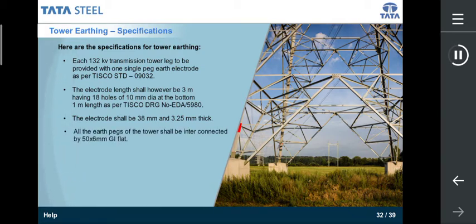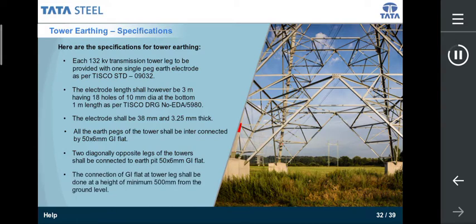All the earth pegs of the tower shall be interconnected by 50 by 6 mm GI flat. Two diagonally opposite legs of the tower shall be connected to the earth pit by 50 by 6 mm GI flat. The connection of GI flat at the tower leg shall be done at a height of minimum 500mm from the ground level. Hope you remember these specifications. Let us continue to the next topic.